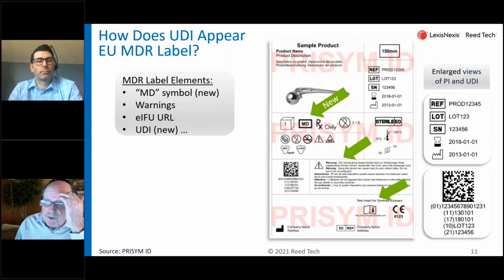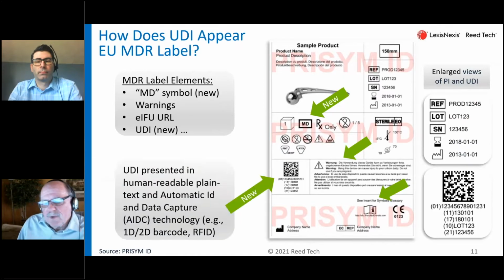I included a sample of a European Union label. We don't have time to go into all the details here, but there are some new things that you ought to be aware of. The MD in a rectangle is brand new for medical device. There's enhanced use of warnings and electronic information for use URLs. But today we're talking about the UDI, and here's where the UDI would be included in this particular sample. Again, space is at a premium, so a 2-dimensional barcode might be a good option for you.